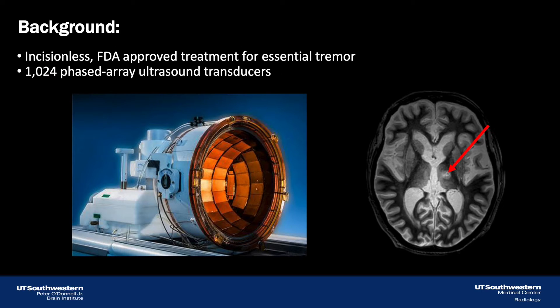MRI-guided high-intensity focused ultrasound thalamotomy is an incisionless, FDA-approved treatment for essential tremor. During the procedure, an MRI-compatible helmet housing 1,024 phased-array ultrasound transducers is used. Those ultrasound elements can be simultaneously focused into the brain to produce a thalamic lesion, indicated by the red arrow in the right-hand image. In producing this lesion, we dramatically reduce tremor in our essential tremor patients.